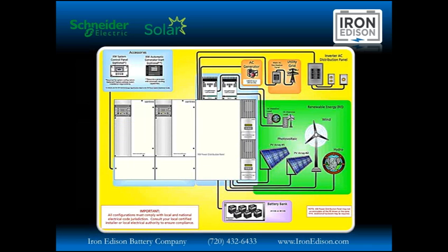So let's take a quick look at the overall design of a Schneider Electric system. What you see on the left-hand side of this diagram is 2 Schneider inverters. In the center is the Schneider XW Power Distribution Panel with 2 60 amp charge controllers. In this diagram, you see we've connected 2 solar arrays. Wind and hydro are also possible. We can connect an AC generator and the utility grid directly into the Schneider inverters. Some of the accessories that we commonly use are the system control panel and the auto generator start.